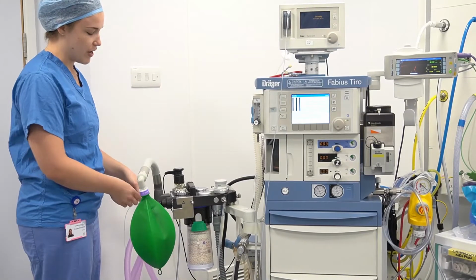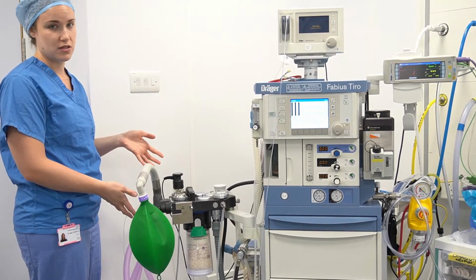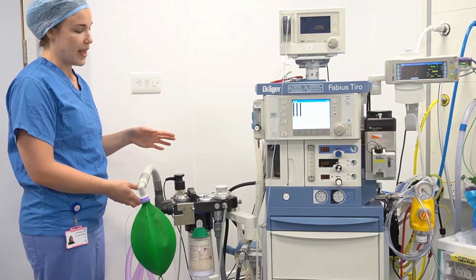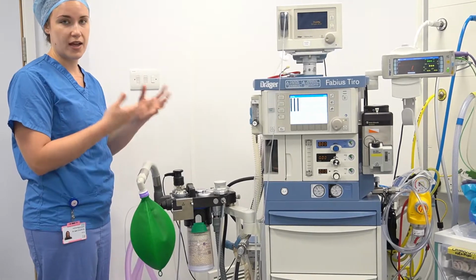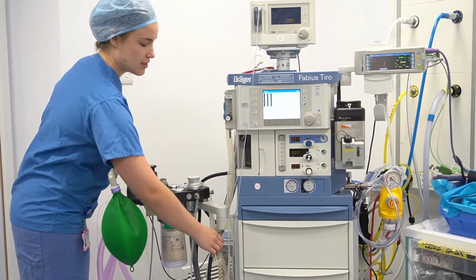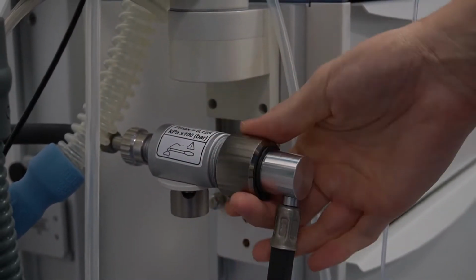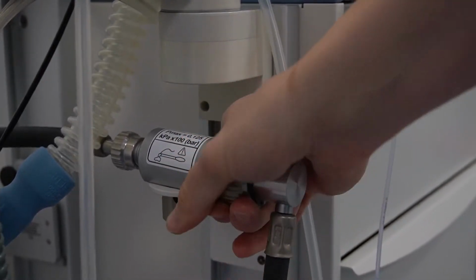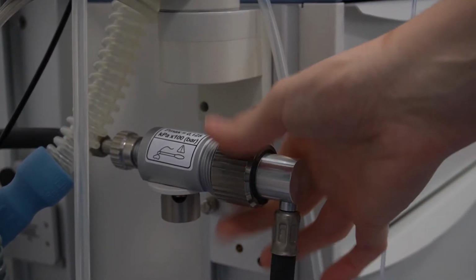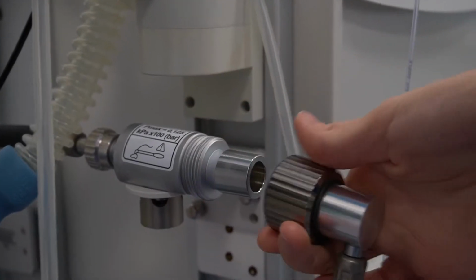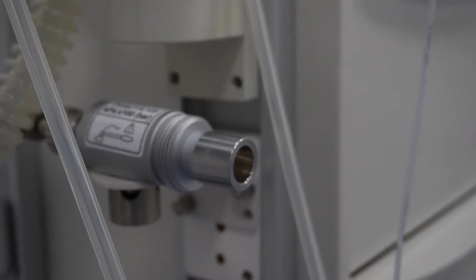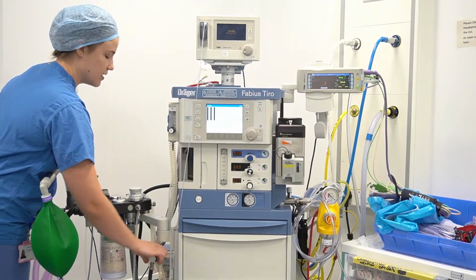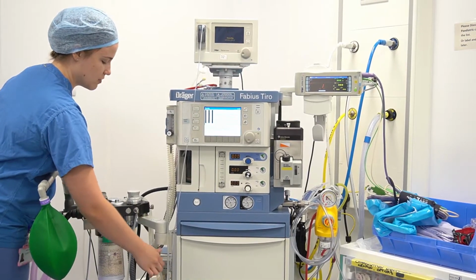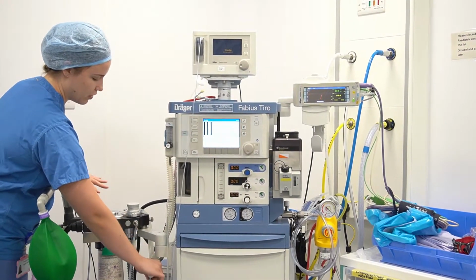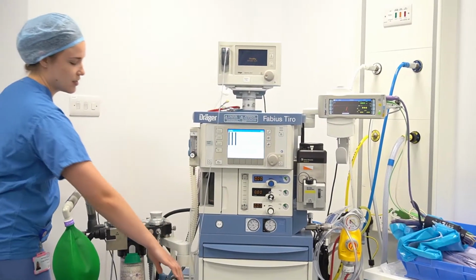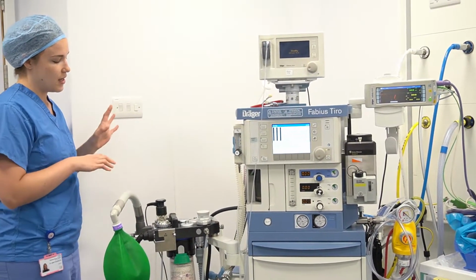And then, as you can see here, we've got a circle system that's connected. If you did want a common gas outlet, what you would do is over here, you untwist this and remove this, and then that would form a common gas outlet over there. So if you were connecting a Bain circuit, for example. And then obviously, once you're reconnecting it, just to make sure that this is now no longer bypassed, you reconnect it, make sure it's tightly connected, and come back here.